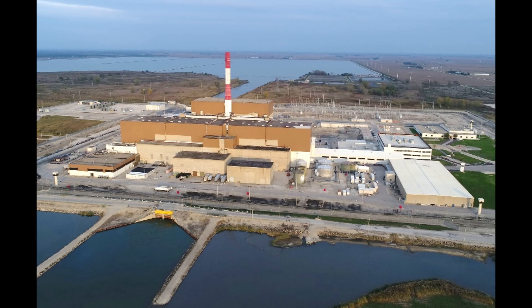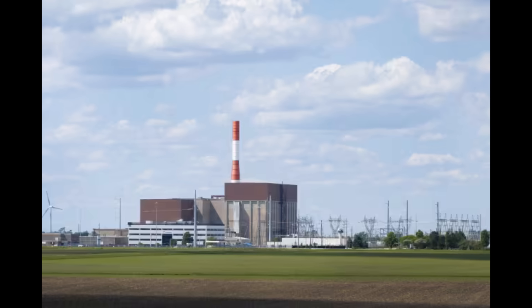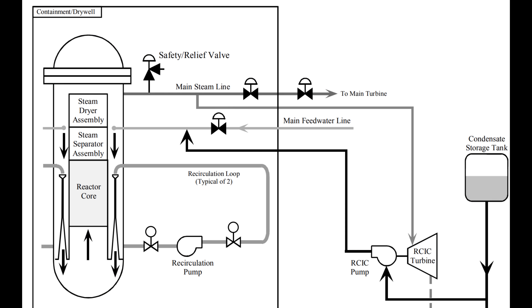Now let's explore the events that unfolded at LaSalle. The date is March 9th, 1988. LaSalle Reactor 2 is being operated in normal conditions, running at 84% power, producing 930 MW of electricity. The core flow rate is at 76% the rated limit, pumping in more than 10,000 kg of water every second. 99% of the control rods are fully extracted, and both recirculation pumps are running, keeping the power stable.